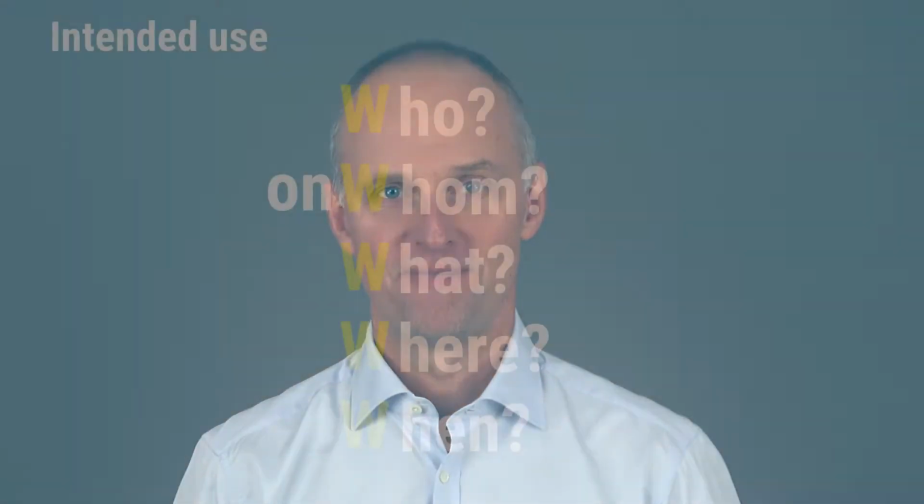Another thing which is important to remember is that the intended use should be defined by you, the medical device manufacturer. And another important thing to note is that intended use is not only a paragraph in the instructions for use, it includes other communication channels as well. For example, what your sales reps are saying about your medical device and what you can say in your advertising. All these things must be aligned.